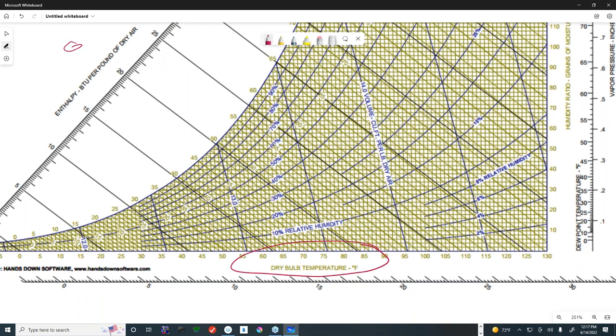So the horizontal scale is called the dry bulb temperature. If you remember a moment ago, we know how to measure the dry bulb temperature, which is with a simple thermometer. The bulb of the thermometer is just dry, and it's basically just measuring the ambient air that we're sitting in. So that's along the horizontal axis. Along the vertical axis is the humidity ratio, and this is in grains per pound of dry air. One of the interesting things about grains of moisture is that there are 7,000 grains per pound of dry air. That's kind of cool, huh? Grains are a very, very small unit for us to use for measurement.